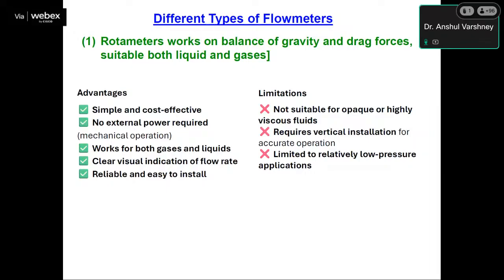These types of flow meters are simple and cost effective. There is no external power required. It can work for both gas and liquids. There is a clear visual indication of flow rate, and it is reliable and easy to install. However, these flow meters are not suitable for opaque or highly viscous fluids. It requires vertical installation for accurate operation, and it is limited to relatively low pressure applications.